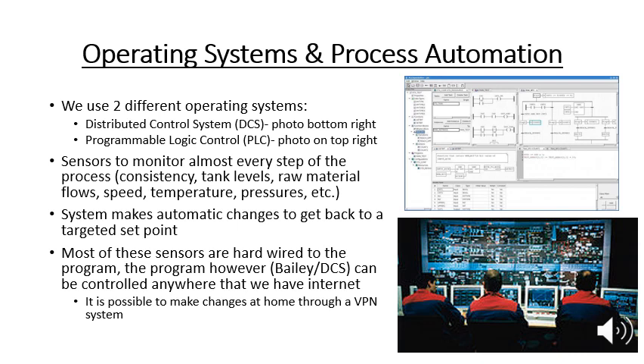Our second operating system is a distributed control system, or DCS. This ties the whole process together, not just a piece of equipment. We have sensors and transmitters installed on most machinery and equipment that are tied into the control loops and provide feedback to our control systems. Our control system takes this feedback and makes changes to get back to the targeted set point automatically. These sensors read numerous things, including raw material consistency, flows, tank levels, machine speed, temperature, pressure, vacuum, equipment position, etc. They are hardwired to the DCS, which improves the robustness of the system.